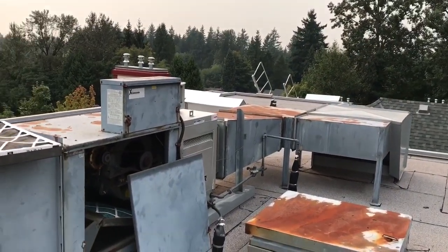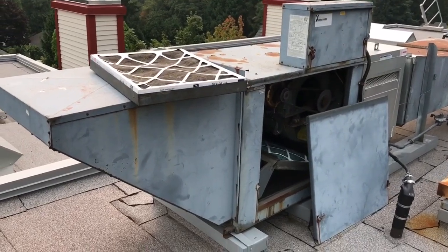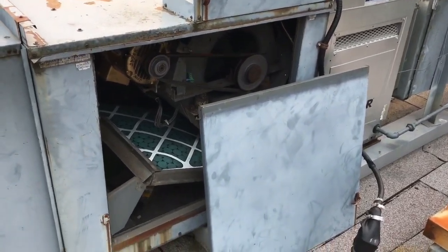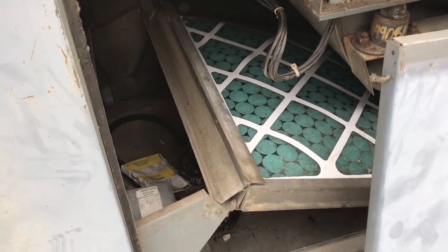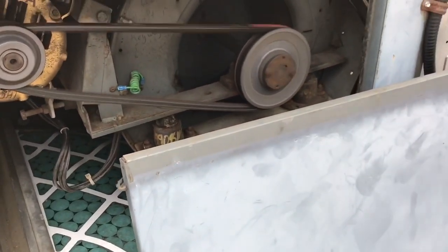Up on this roof we've got this big HVAC unit that's about 24 years old. It's an Engineered Air product, but what I don't see on it is a maintenance sticker. So I've opened it up and pulled out the filter. You can see what the backside of that filter looks like — it's really clean. Obviously the filter is doing a good job and it seems to be operating properly.